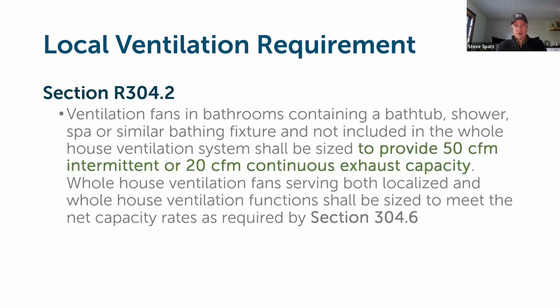So we're talking about a whole house ventilation system with the intent being here that you have ventilation air moving throughout the building. And then in conjunction with that, there are minimum performance requirements for local ventilation. And what local ventilation means: point load moisture sources, rooms in the building, bathrooms that have showers, baths, etc. Those bathrooms need to have a minimum capacity of at least 50 CFM of ventilation air if the whole house system is going to be run intermittently, meaning it's coming on for say 20 minutes per hour or 30 minutes per hour on a timed basis, something like that.